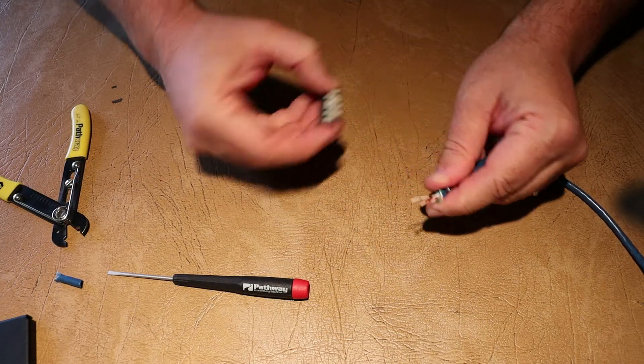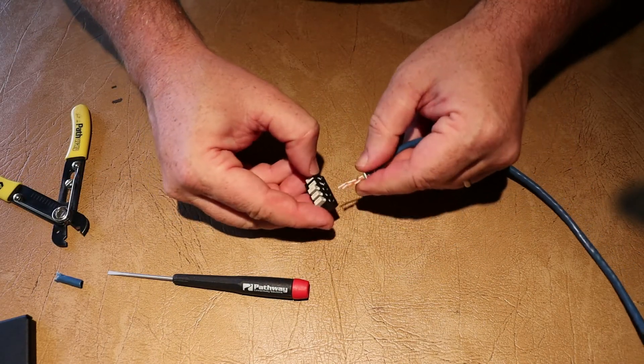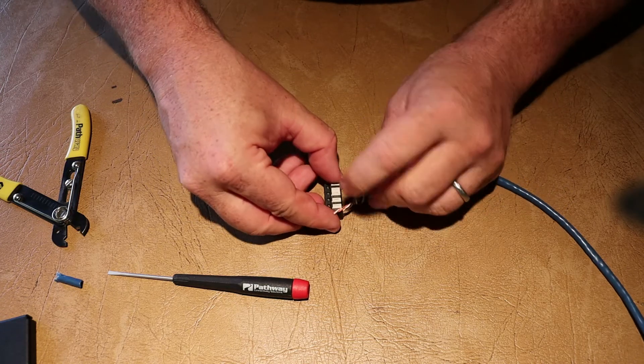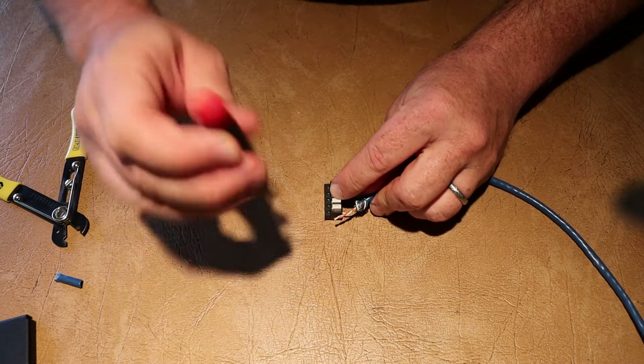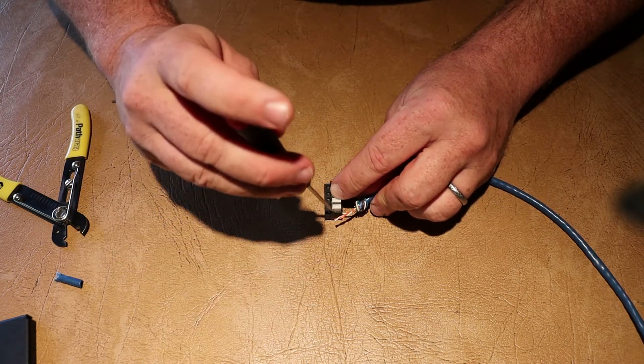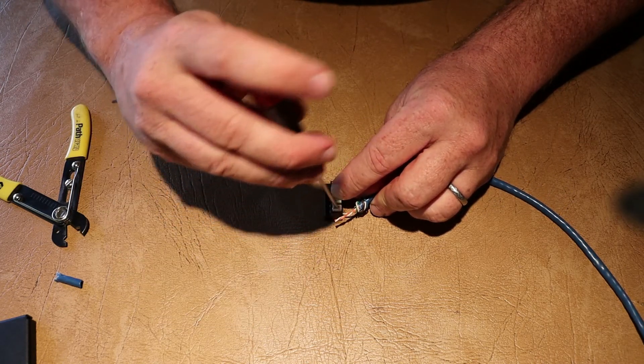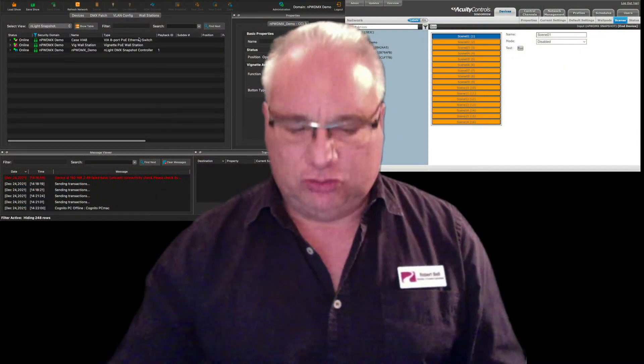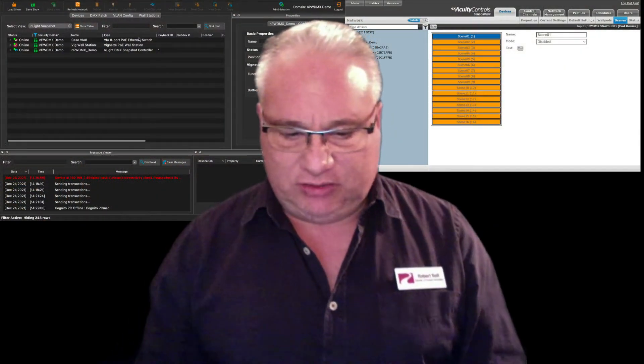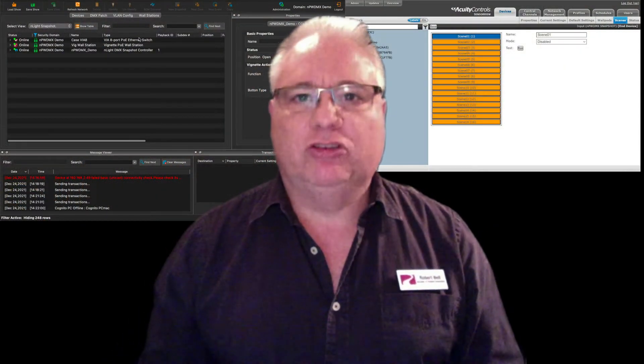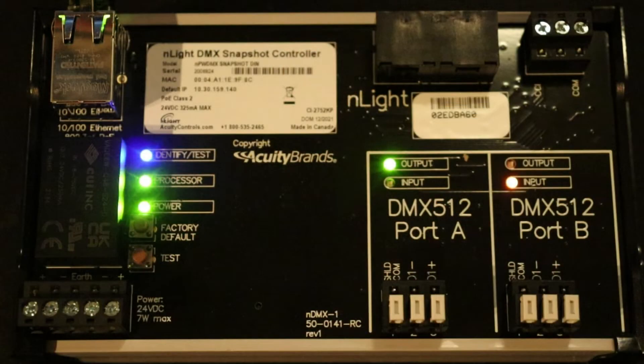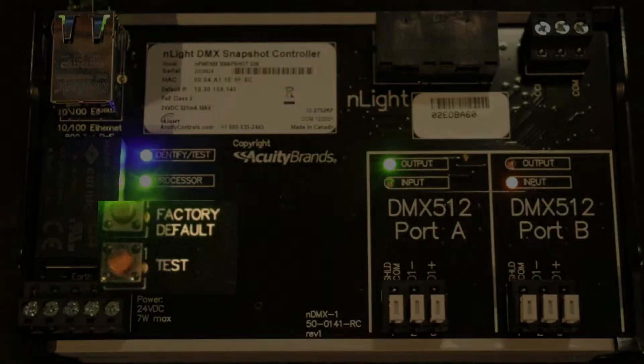They have the removable connectors, either compression screw or my favorite, the IDC—the insulation displacement contact connector—which is great when you're using solid core category cable because there's so much less stripping and you get a very good contact. We also discussed in the last video the test button, and if you hold the factory reset for five seconds you're going to be back at square one.